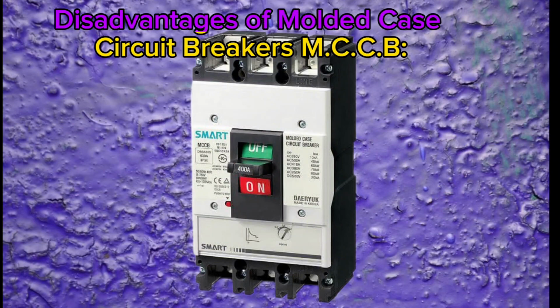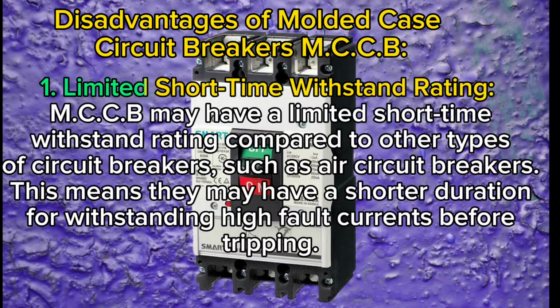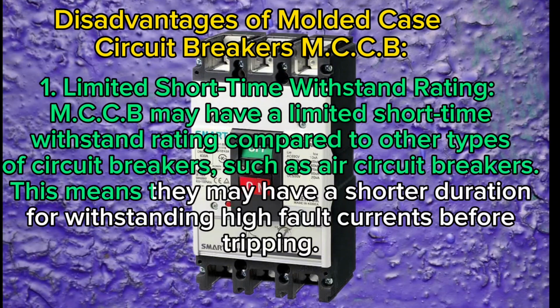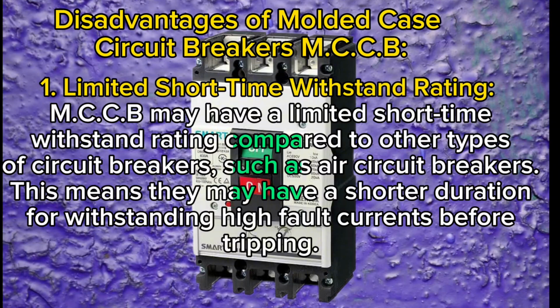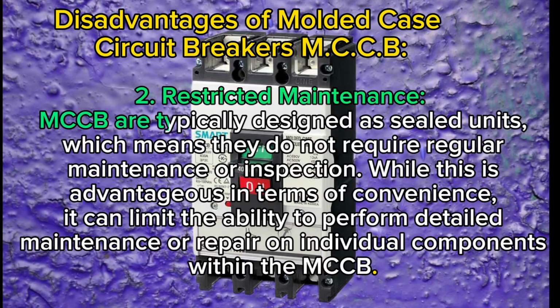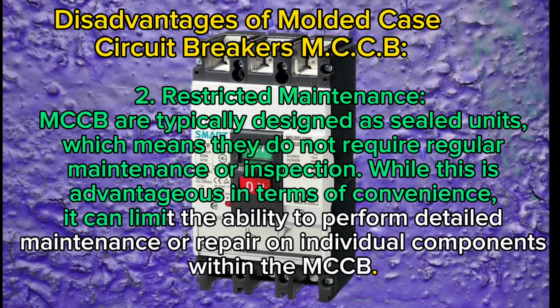Disadvantages of molded case circuit breakers, MCCB. 1. Limited short time withstand rating. MCCBs may have a limited short time withstand rating compared to other types of circuit breakers, such as air circuit breakers. This means they may have a shorter duration for withstanding high fault currents before tripping. 2. Restricted maintenance. MCCBs are typically designed as sealed units, which means they do not require regular maintenance or inspection. While this is advantageous in terms of convenience, it can limit the ability to perform detailed maintenance or repair on individual components within the MCCB.